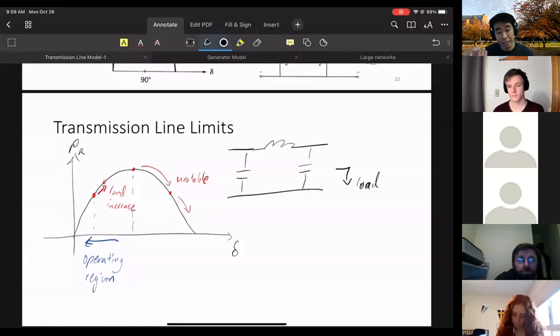Okay. So it's called the line stability limit because when this kind of thing happens, sometimes it's hard to tell, because your line may be very much under its current limit. The current may not be all that high, but still you cannot transfer any more real power. And you want to always stay under this limit. Most of the time, this is what stops us from sending power. Any questions on this stability picture?